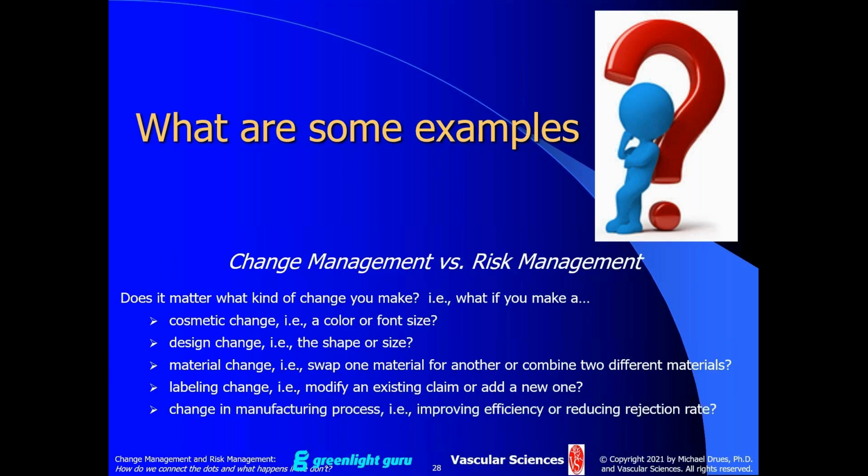And finally, a change in the manufacturing process. Now, in the 510K and de novo worlds, there is not, at least not yet, a requirement to put in the 510K or de novo submission any information about the manufacturing process, but there is in the PMA world. If you have a PMA, FDA wants to see some information.